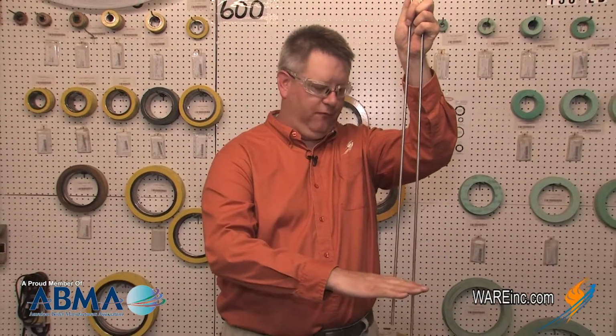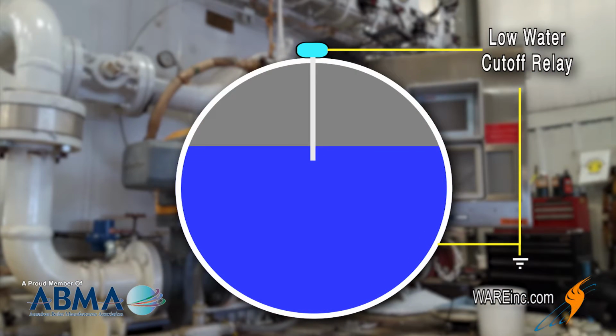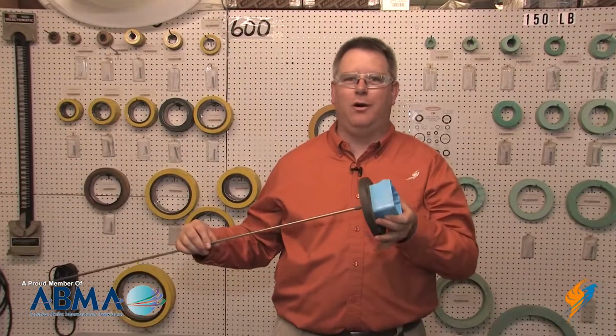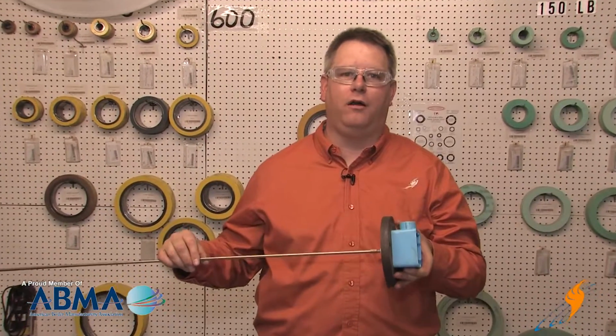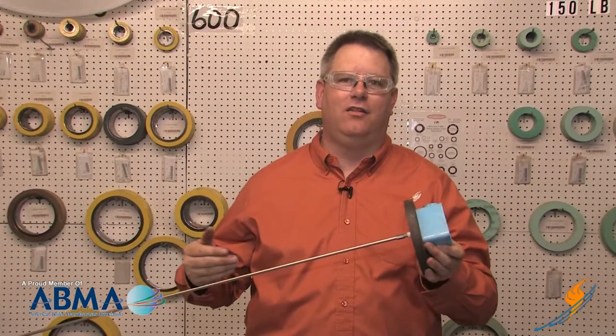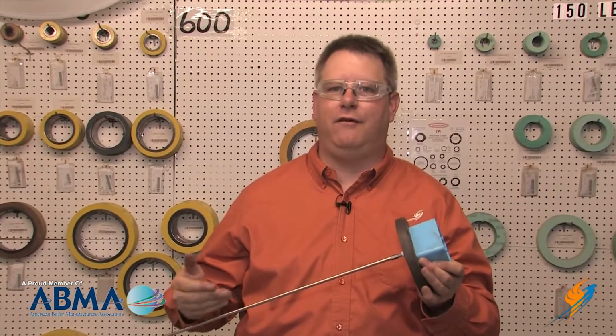The way this operates is as the water rises and forms a junction between the two probes, that connection is recognized by the relay, and it pulls in and completes either the operating limit circuit or a high water alarm, whatever the case may be. Understanding how these components work together is an important part of checking the safeties on your boiler and having safe operation.